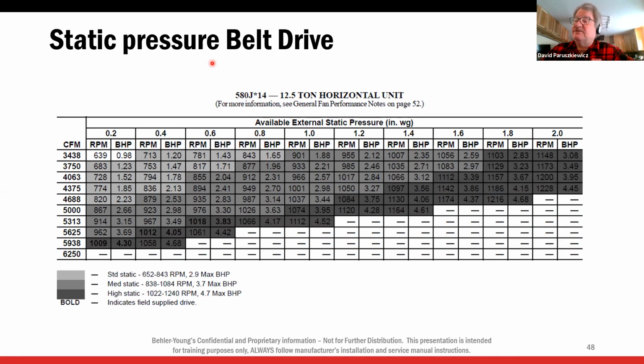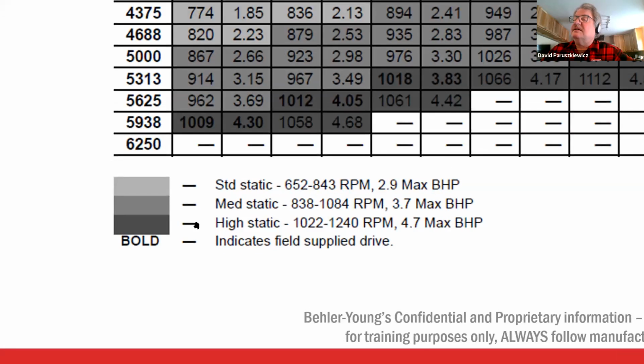Static pressure on these belt drive units. Now, standard static, if you look down here, I'm going to zoom in so everybody can see this: standard static, medium static, high static. This is how a unit is ordered. In the larger units, we typically stock the medium static. Now, what does that mean? It means the static range they can operate under.